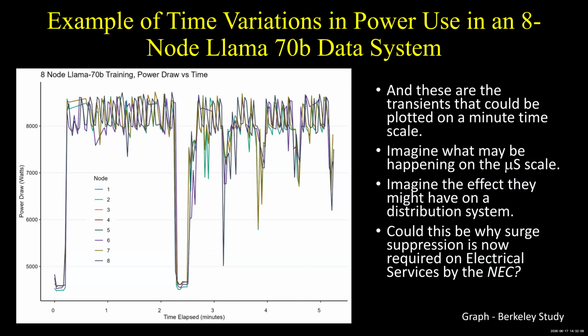Every photovoltaic job we design, because we're tying something into the main service, we need to require them to install a surge suppressor. So if it's an old system that didn't have one, it's going to have one after our PV system goes in, and it isn't because of the PV system, it's because NEC requires it for all new systems. But that's a good point, and that probably is the main reason.